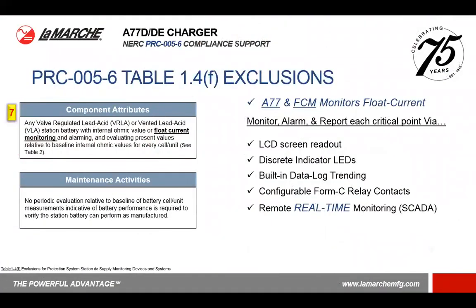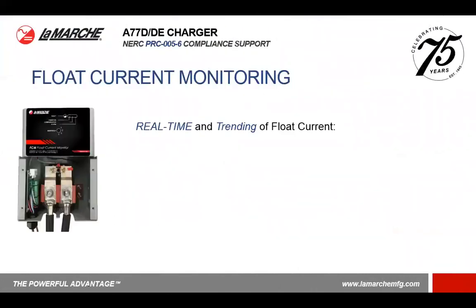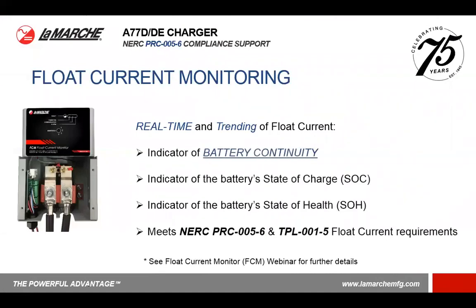In addition to this, point number 7, we have to monitor for float current on the battery system. Well, the A77 and the FCM products do monitor for float current. Real-time and trending of float current is the ultimate indicator of battery continuity, the battery state of charge, and it can indicate the battery's state of health. This will meet the PRC-5 and the TPL-001-5 requirements for float current.